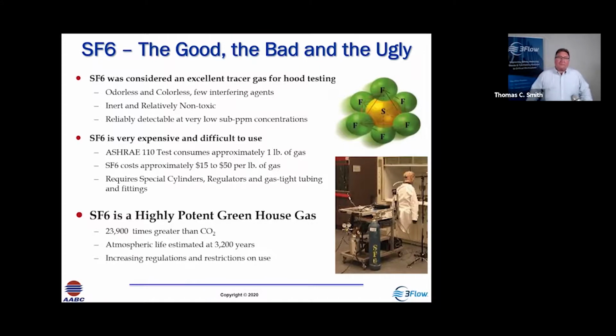Now, one of the things that we learned about SF6, sulfur hexafluoride, is that it was an excellent tracer gas for conducting hood tests. It's odorless, it's colorless, there's very few interfering agents, it's inert, it's very stable, and it's detectable at really low concentrations. The problem is it's expensive, and it's an extremely potent greenhouse gas. And so it's 24,000 times more potent than CO2 as a greenhouse gas.